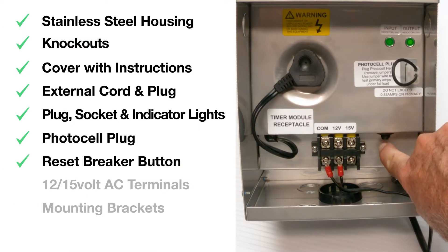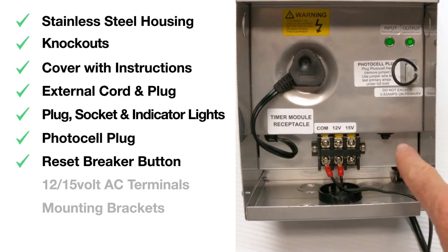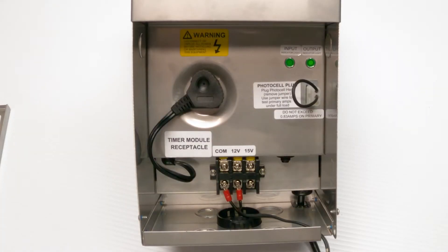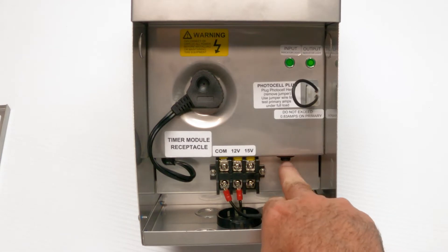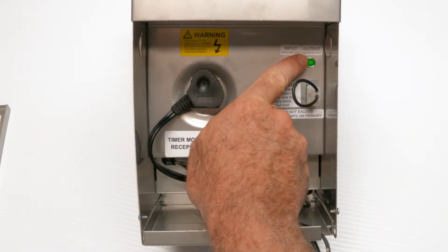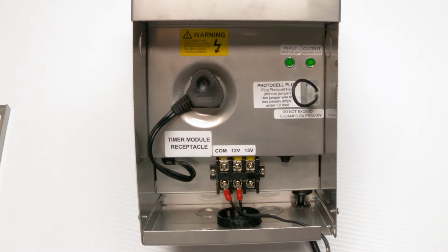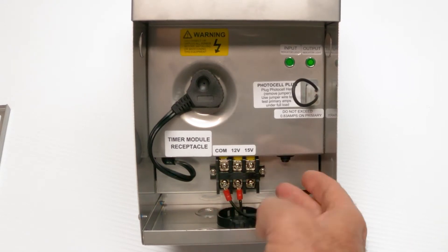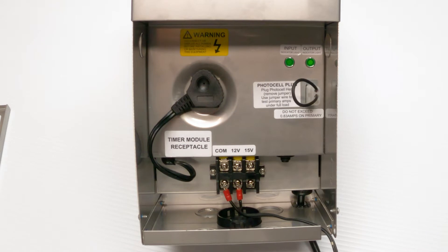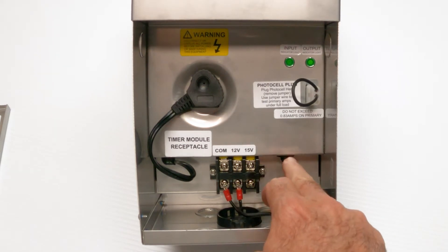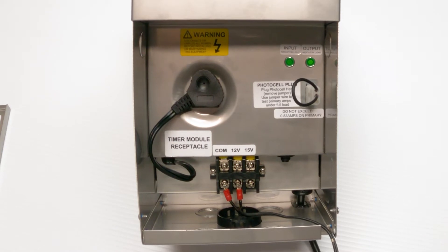So down here is a reset button. And this pops out a little bit when you have a short in your landscape lighting line somewhere. So if that button's out, that means it's not producing electricity, then your lights aren't working. So the test for that is to remove your landscape lighting wire that's going out to the field, remove it here, push the button back in and see if the lights come back on. If when you put this back on, it pops out again, you have a short out in the field and that needs to be addressed.